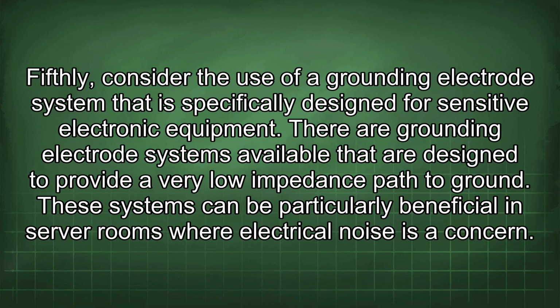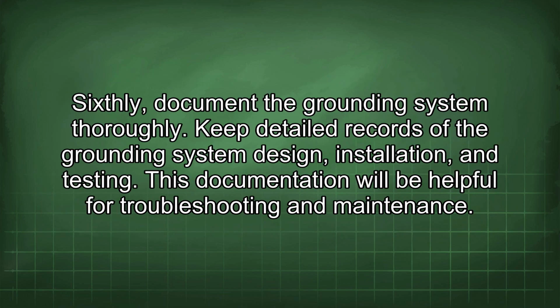Fifthly, consider the use of a grounding electrode system that is specifically designed for sensitive electronic equipment. There are grounding electrode systems available that are designed to provide a very low impedance path to ground. These systems can be particularly beneficial in server rooms where electrical noise is a concern. Sixthly, document the grounding system thoroughly. Keep detailed records of the grounding system design, installation, and testing. This documentation will be helpful for troubleshooting and maintenance.